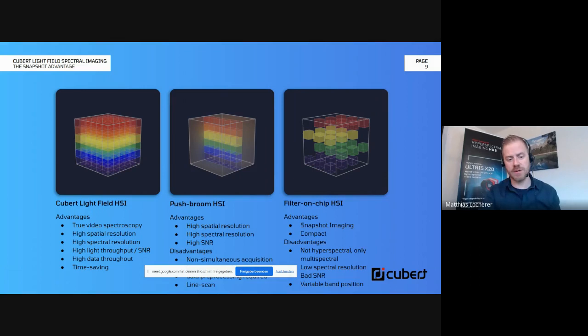This really allows true video spectroscopy. You have high resolution data, but I'll speak about that later as well. A high light throughput, leading to a very good signal to noise ratio, and this is, of course, time saving. Push broom, the classic approach. Here you definitely will find the highest spatial as well as spectral resolution. It's a technique that is more than 40 years old now, still providing very accurate data. However, you need to pre-process the data before you can work on a data cube, because it's scanning. Scanning means you either need to move your samples underneath the camera, like on a conveyor belt, or your camera needs to move above the ground, like from an aircraft, for instance.